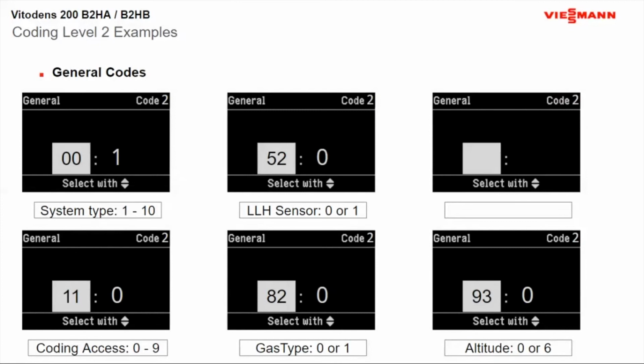Your 00 is your system type. So I always like to talk about your system type. Remember, everything's auto recognized. So I can tell right here that my domestic on 00 is not tied in. The reason why I say that is because when domestic is tied into this boiler, I always have an even number on that 00. So if I had a 2 here, I know I would have domestic tied into this boiler.